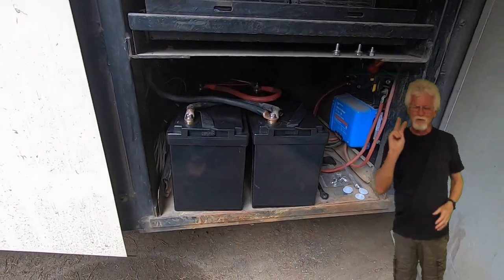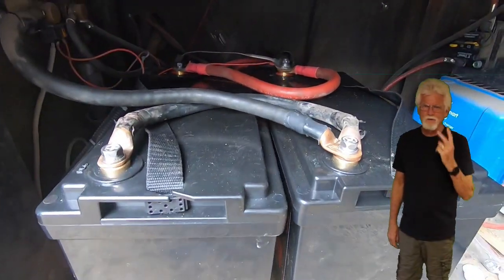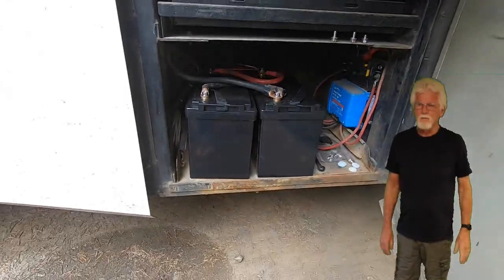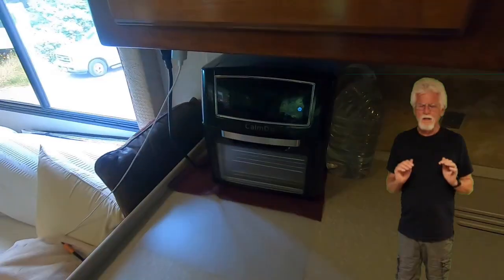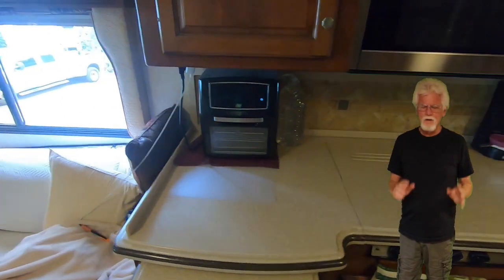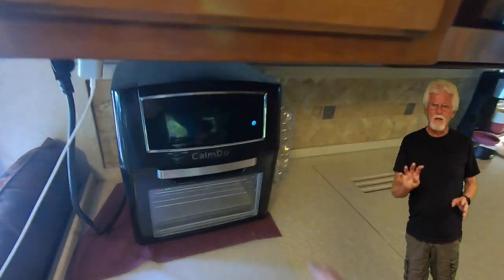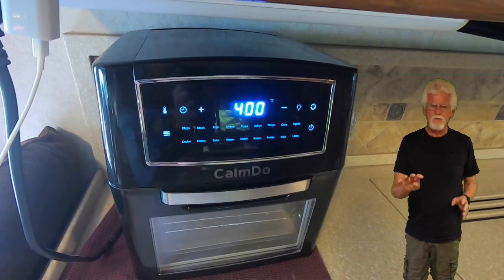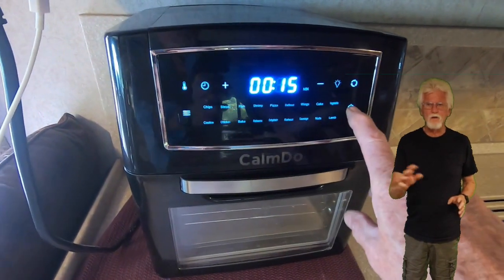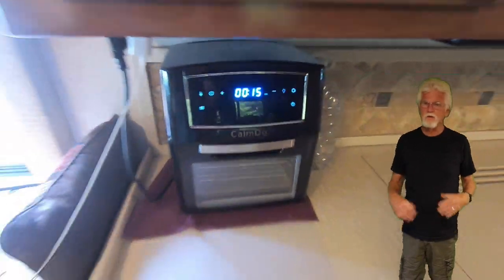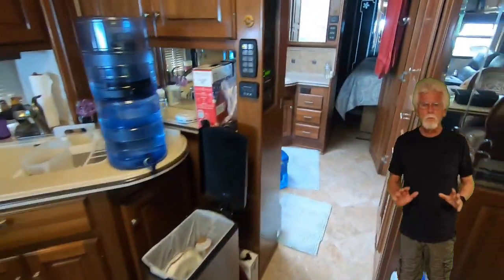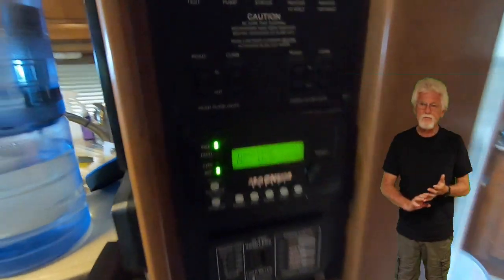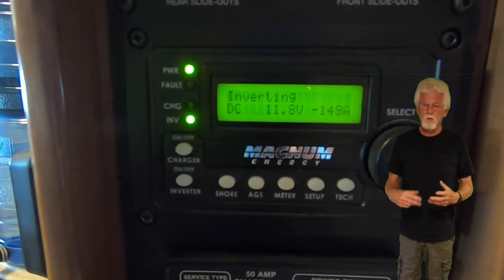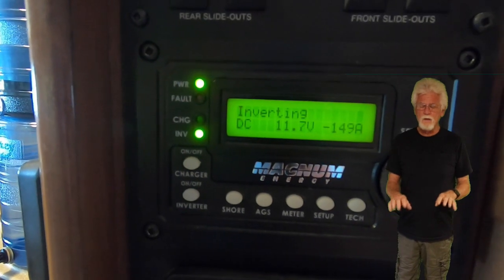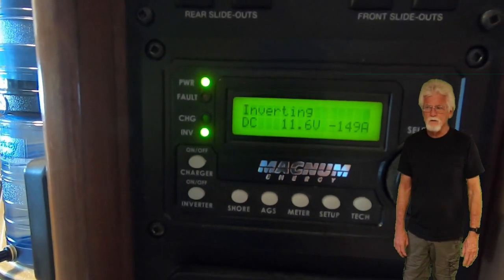Alrighty, we have 2 batteries down in the battery compartment. That's 200 amp hours. But we're still being really unfair to Dr.Prepare, as our Magnum inverter clearly says that they recommend 400 amps of batteries to run loads over 1,000 watts. But this is a test. This is a product review. We want to push it to the max and see what happens. I want to see if our Magnum inverter is working and shutting things off if need be, and I want to see just what these batteries can do.